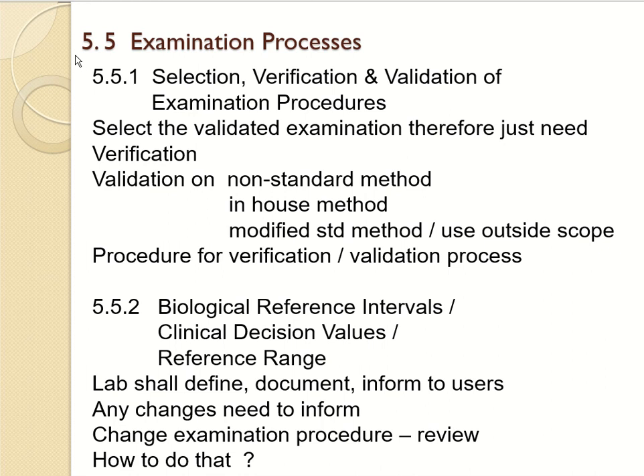Okay, under 5.5 examination processes, clause 5.5.1 defines the selection, verification and validation of examination processes. So the lab should select validated examinations. Therefore, the lab only needs to do the verification, and for non-standard methods or in-house methods and modified standard methods used outside the scope, the lab needs to do the validation of the test itself. So there should be a procedure for the verification and validation process.